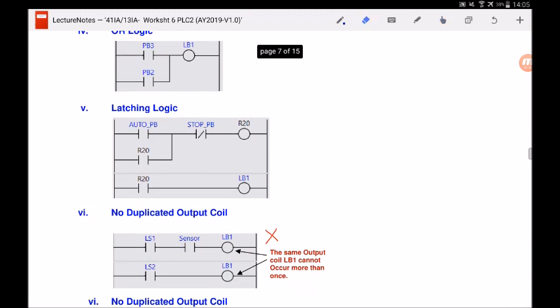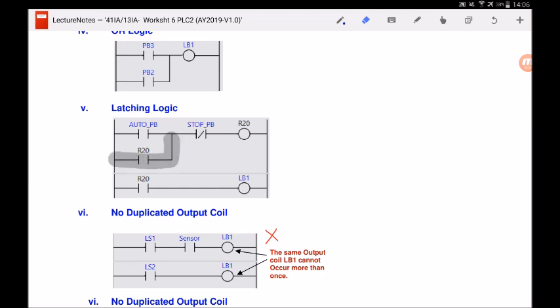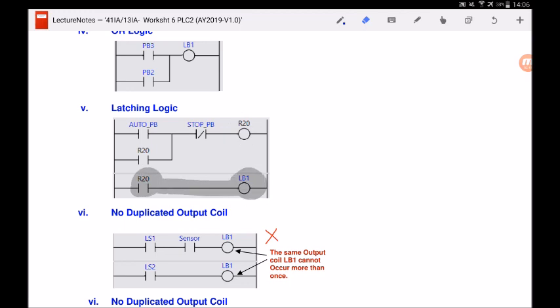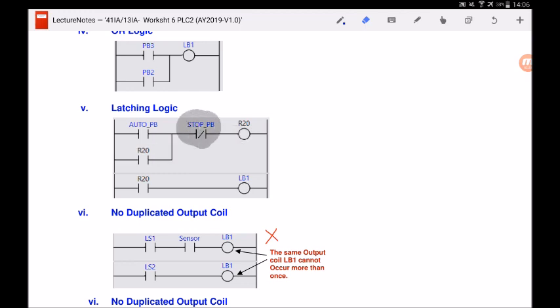For the latching logic, we use an internal software relay of the PLC called R20. When 'auto_pb' is pressed, R20 turns on and the contact closes, providing the latching logic so R20 stays on even when the button is released. The light bulb then remains on due to this latch. Only when the stop button is pressed does the normally closed contact open, turning R20 off so the light bulb goes off. This is the same latching logic taught earlier in electrical hardwired diagrams.